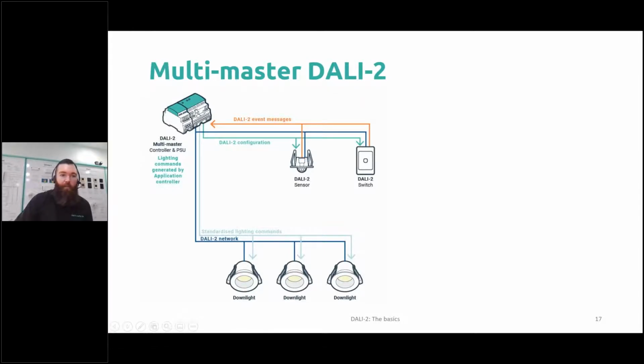So we'll move over to the role of the application controller. What is it going to do in this scenario? Well, it's just heard from sensors 4 and 5 that it's got occupancy. It's going to listen for that occupancy, look up in some internal logic, and say, okay, those sensors are in group 4. I'm going to turn group 4 on, and start a timer where after 15 minutes I'll turn them off. If I don't hear from address 5 or 4 again, I'll turn the lights off. But if I hear a motion event from either of those devices, I'll reset that timer and keep going.